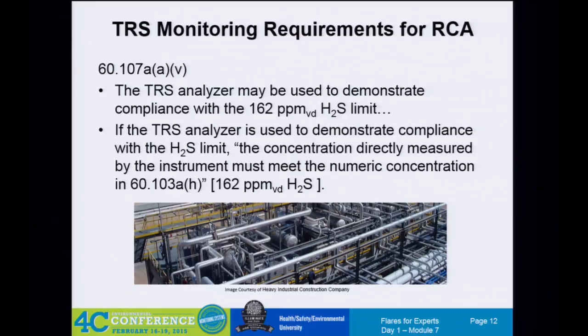With your H2S monitor for RCA, the biggest difference was the 10-day sampling and continual weekly sampling. If you're out of the 95% confidence, you have to do another 10-day event. People start asking, if you have a water seal, where do you take that sample? Upstream of the drum, where you get varying concentrations, or downstream of the water seal, where you might be sampling purge gas all the time? There are pros and cons to each.